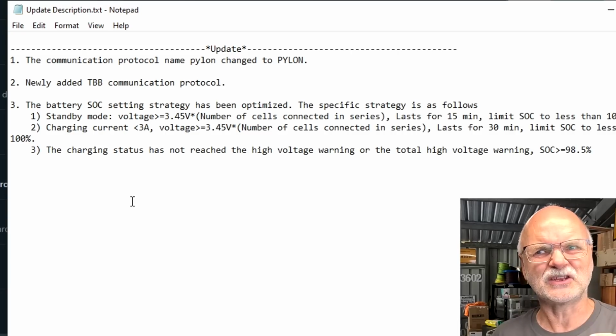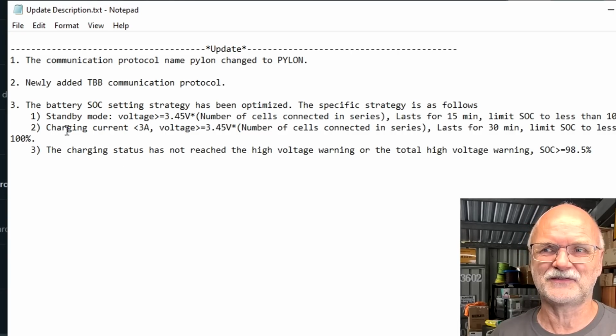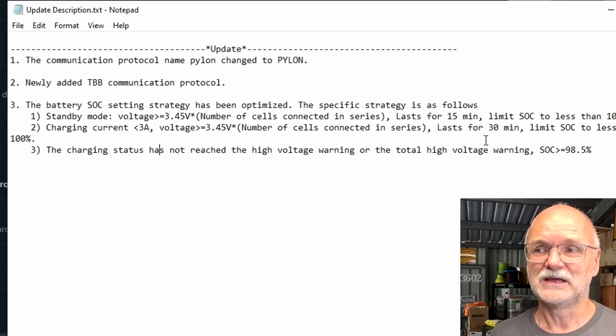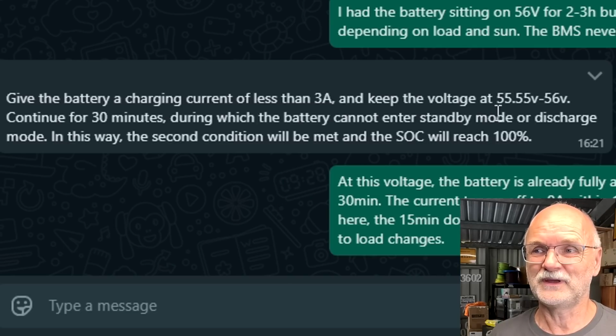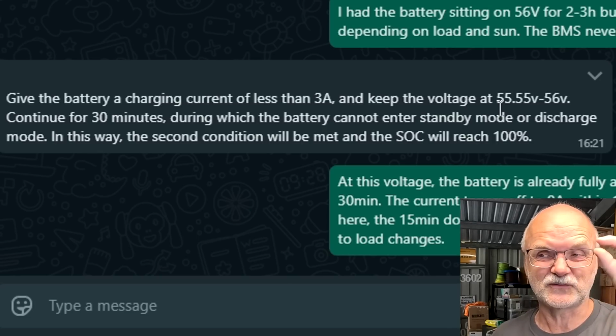I think they've changed this up a little, because now it says charging current under 3 amps, voltage over 55.2 volts for 30 minutes. It doesn't have this window anymore between 55.55 and 56 volts. It was a very small voltage window, and to keep the battery between 55.55 and 56 volts while still charging 3 amps into this battery just will not work. The voltage will rise over 56 volts, and then we are outside of this window.